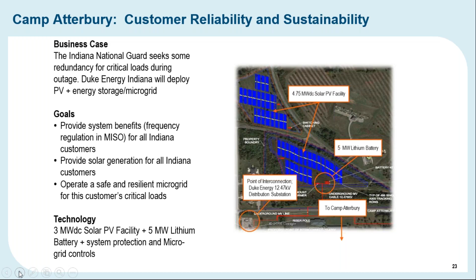So where we've run into challenges with these pilot projects is how the microgrid interacts with the rest of the grid — the protections, the control schemes, the communications and the monitoring. Those have been the biggest challenges. It's not a question of whether the microgrid can work — generally, yes — but how it interacts with the rest of the grid and the existing protection and control schemes is where we've had by far the most learning with these projects.